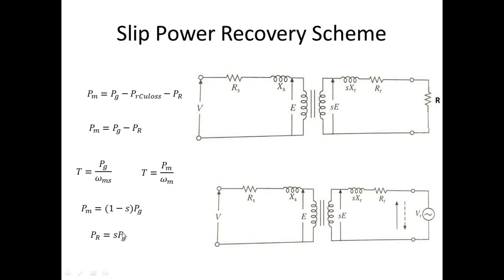In rotor resistance control, this slip power s × Pg was wasted. In the slip power recovery scheme, we recover that power — hence the name. Since Pr is always positive, speed control is below rated speed. However, if we reverse the polarity of the injected voltage source, Pm can exceed Pg, allowing speed control above synchronous speed. This recovered power is utilized only in slip ring motors.